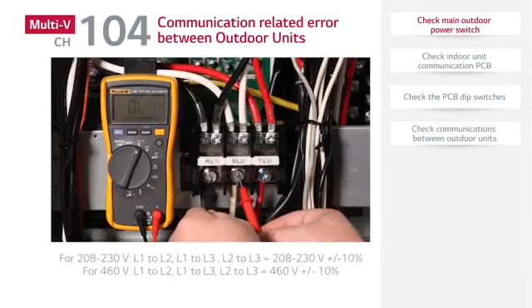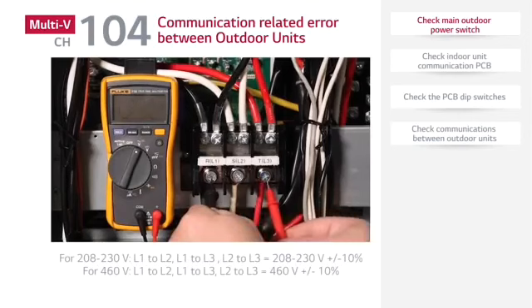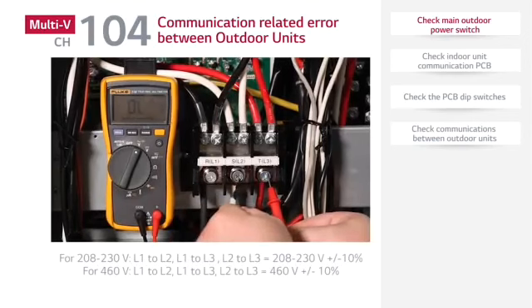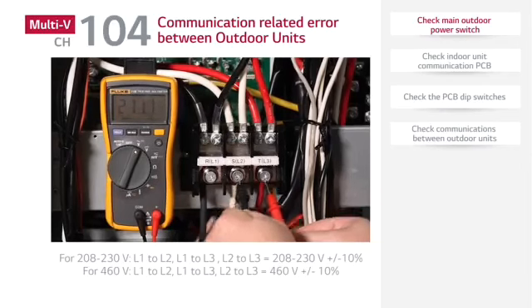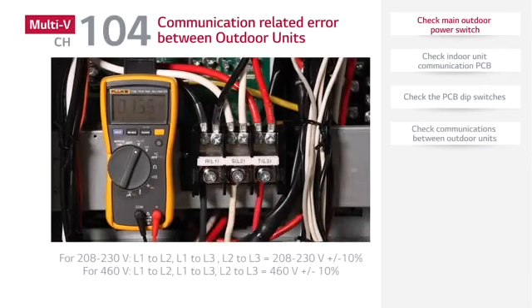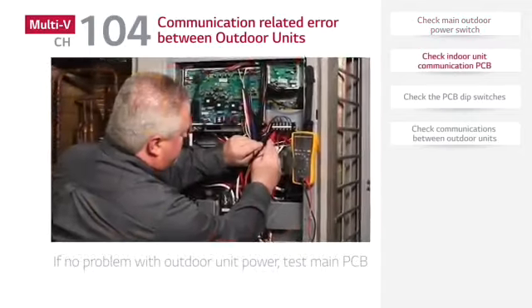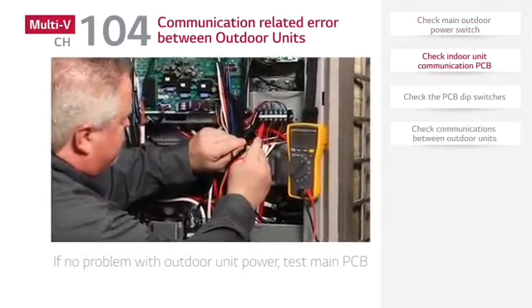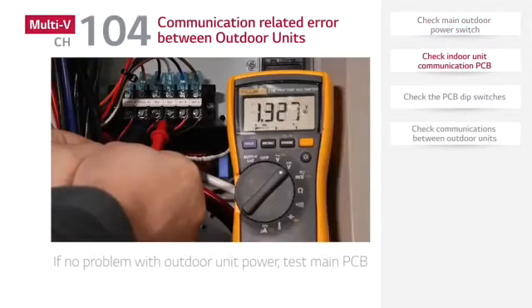For 208 to 230 volt units, L1 to L2, L1 to L3, and L2 to L3 readings should be 208 to 230 volts plus or minus 10%. And for 460 volt equipment, L1 to L2, L1 to L3, and L2 to L3 readings should be 460 volts plus or minus 10%. If there is no problem with the outdoor unit power, test the main PCB.